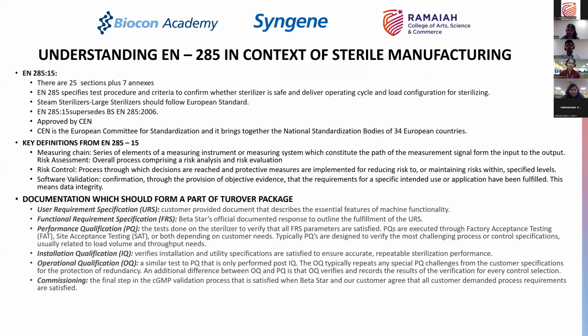So when you go into the industry, when you are trying to qualify as a quality person or as a manufacturing person evaluating any of your autoclaves which are supplied to the plant or are in the process of being procured, then making sure that it is compliant to EN 285, understanding EN 285 yourselves, and making sure that the equipment has been designed as per the requirements of EN 285 is very important, because if it is, then it actually takes care of a lot of the issues that we spoke about. Okay.